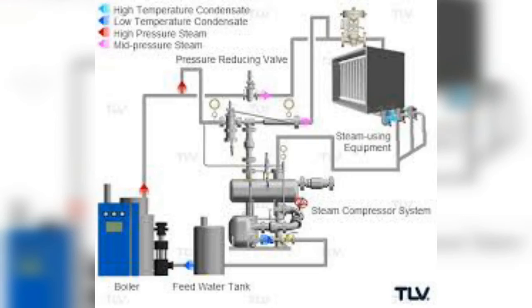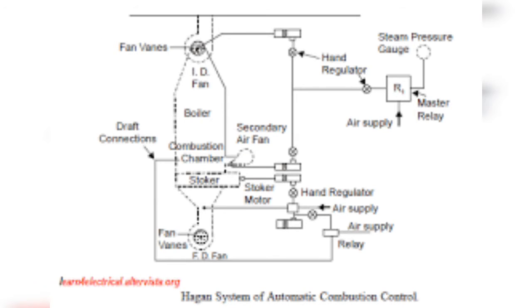The system of automatic combustion control is shown. The master relay R1 is sensitive to small variations in steam pressure and is connected to the steam pressure gauges. A fall in pressure operates the master relay R1, which in turn operates a servo motor coupled to the vanes of the induced draught fan, opening it slightly.